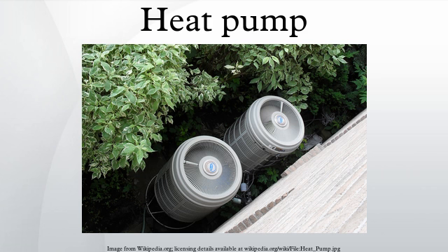Heat pumps are already at a price disadvantage when it comes to initial investment compared to conventional heating solutions like boilers, so the drive towards more efficient heat pumps and air conditioners is often led by legislative measures on minimum efficiency standards. In cooling mode, a heat pump's operating performance is described in the US as its energy efficiency ratio or seasonal energy efficiency ratio, and both measures have units of British thermal units per hour per watt, where 1 Btu/h/W equals 0.293 watts per watt.